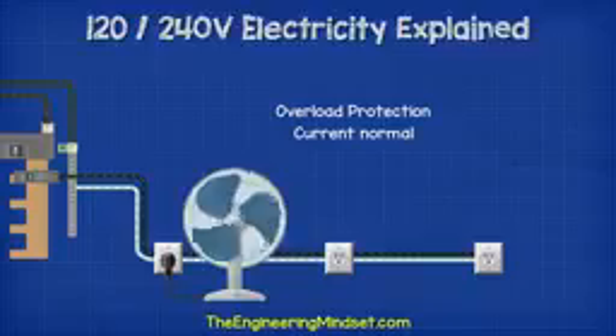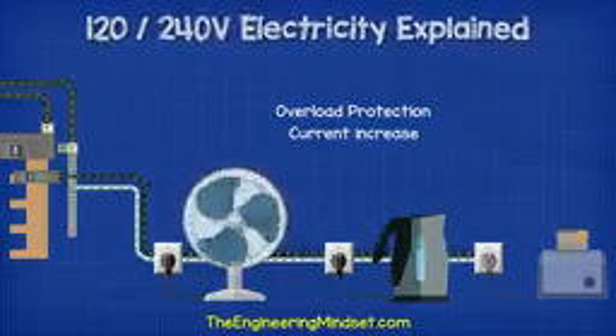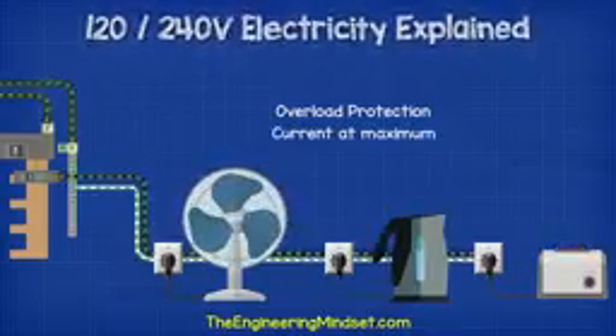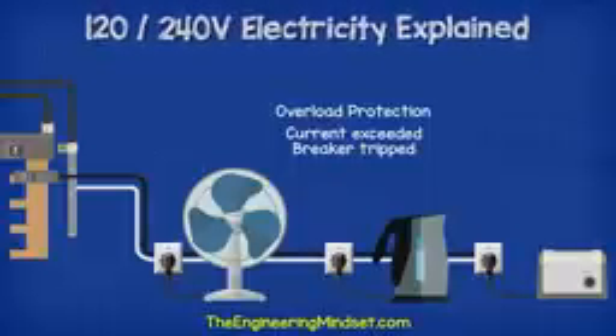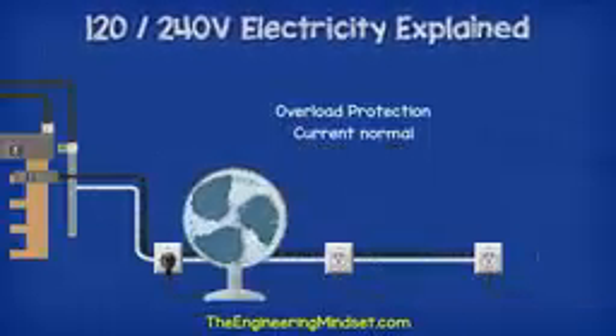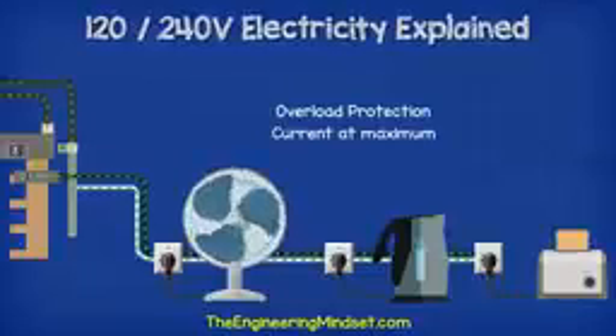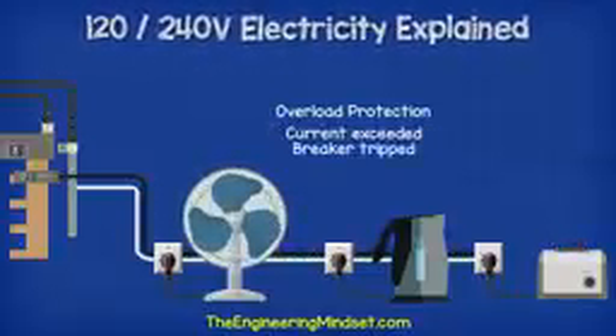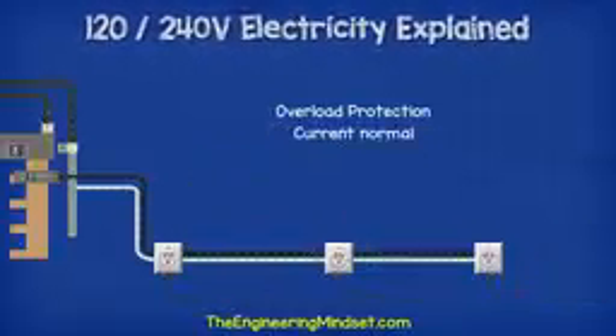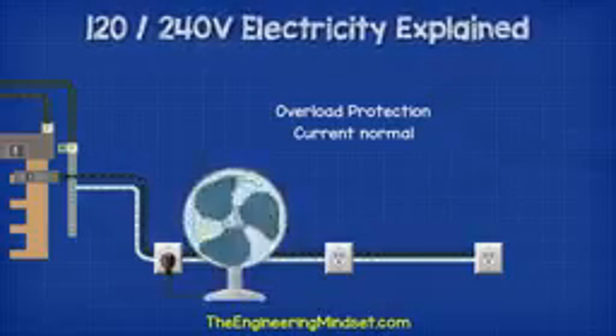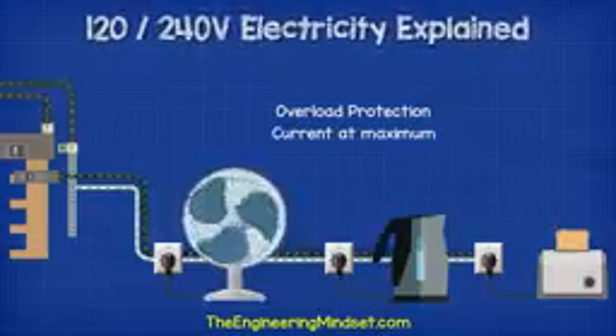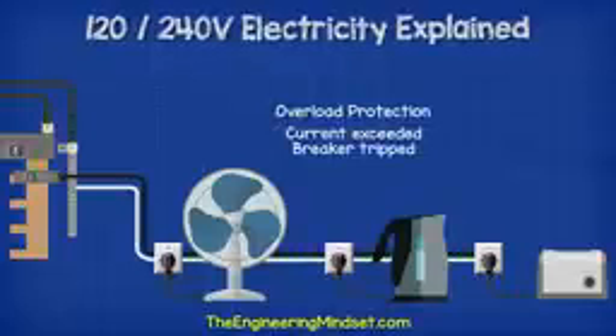The first feature is overload protection. The circuit breaker is rated to handle a set amount of electrical current. When appliances or lights are connected to the circuit, they will each increase the current in the circuit. If too many things are plugged in and turned on, then eventually the current will be more than the breaker can handle, and the breaker will automatically trip to cut the power off to the circuit and protect the property.